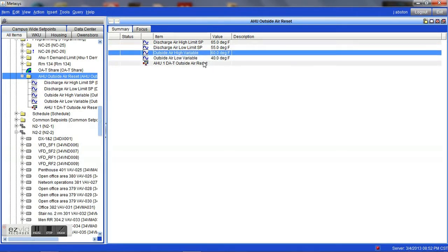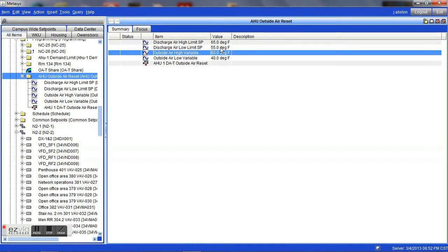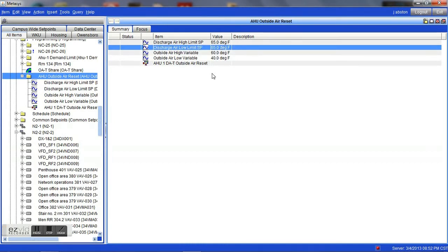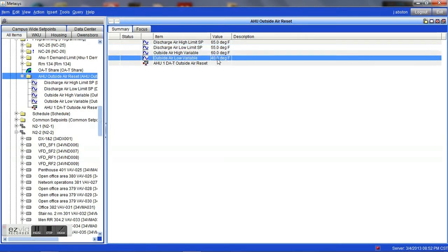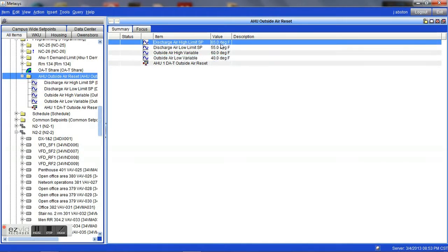Some of the basic principles of this are when our outside air temperature is at 60 degrees or above, we want our discharge air temperature to be at its minimum, 55 degrees. If we are at 40 degrees or below, we want to be at our maximum discharge air temperature of 65 on this particular unit. That can be higher or lower, just depending on your building needs.